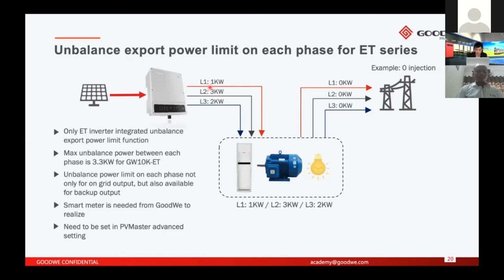So you can find here the inverter will output 1 kilowatt for phase 1, 3 kilowatt for phase 2, and 2 kilowatt for phase 3. In this case, there is no power to the grid on each phase, but the inverter can also generate the maximum power to the loads. So that's why we say it's the premium function of our ET series hybrid inverter.